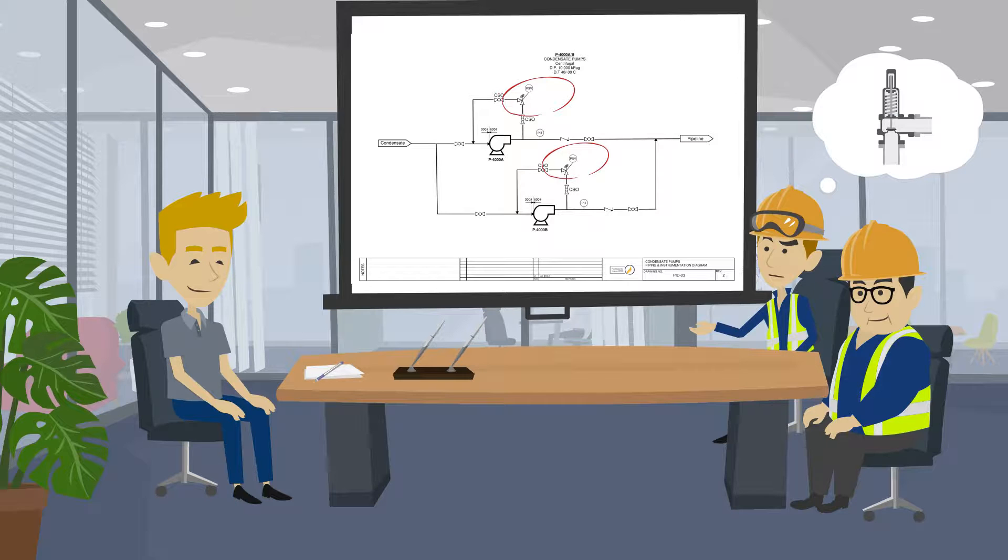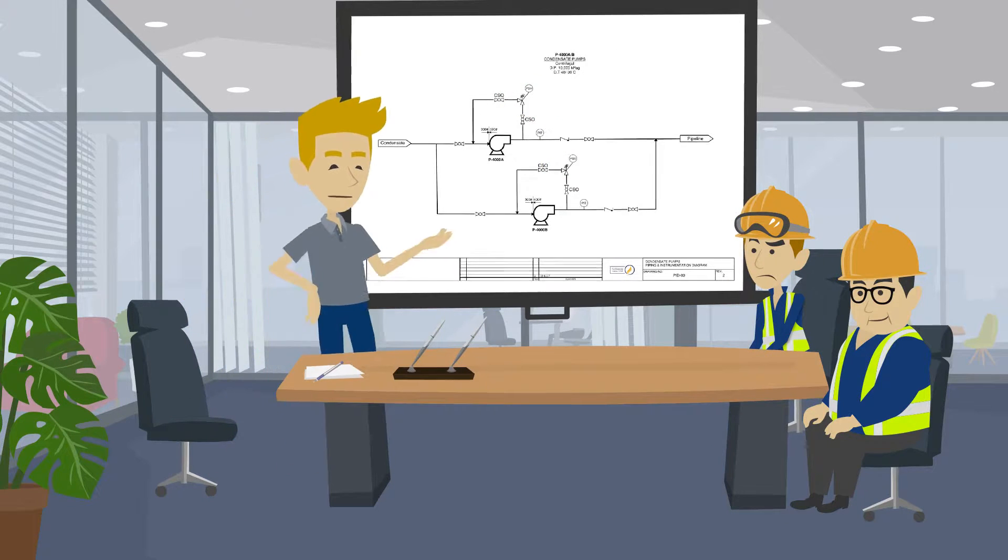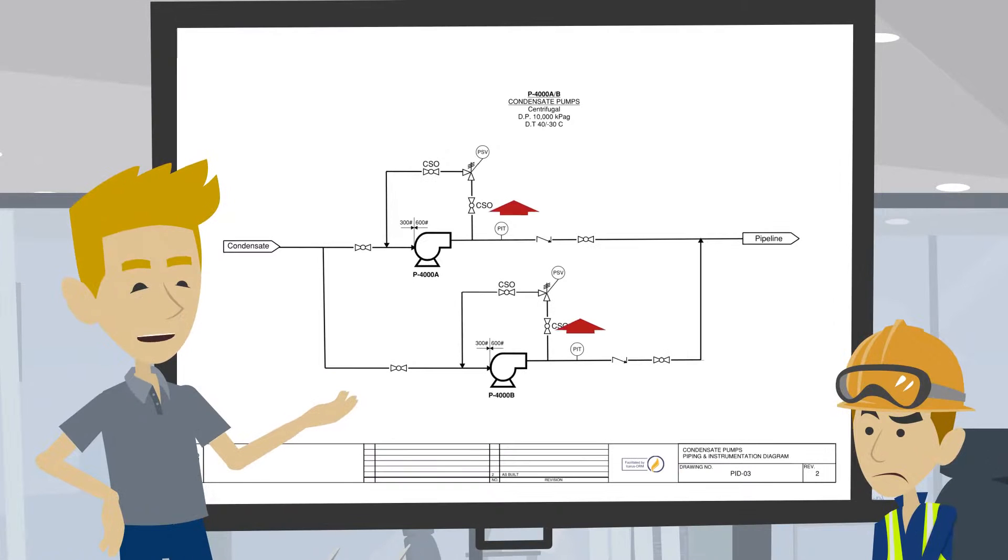What about the PSV? I see one at the pump. The PSV at these pumps relieves from discharge to suction and is designed to recycle flow when the pump is on. It would not be an effective safeguard to prevent an overpressure from happening in a reverse flow scenario.